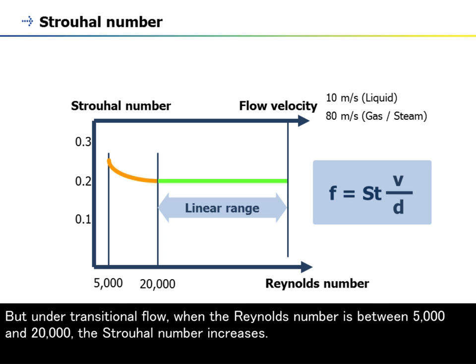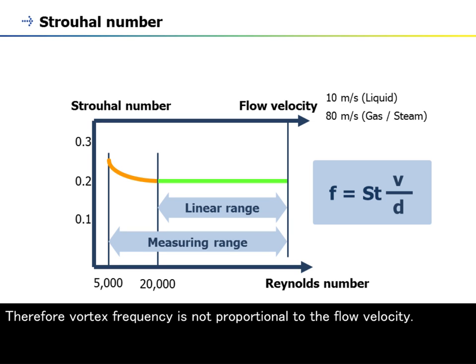But under transitional flow, when the Reynolds number is between 5,000 and 20,000, the Strouhal number increases. Therefore, vortex frequency is not proportional to the flow velocity.